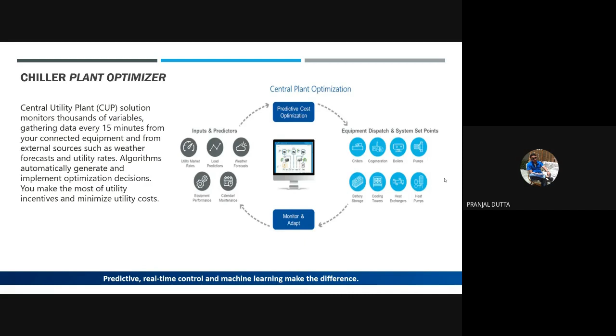Cost mostly means energy cost. So it will dispatch system set points for chillers, cogen points, boilers, and pumps. So it will dispatch a set point. It will change the set point based on the ambient conditions, based on the load side, based on all the data taken from the BMS. So machine learning works this way.